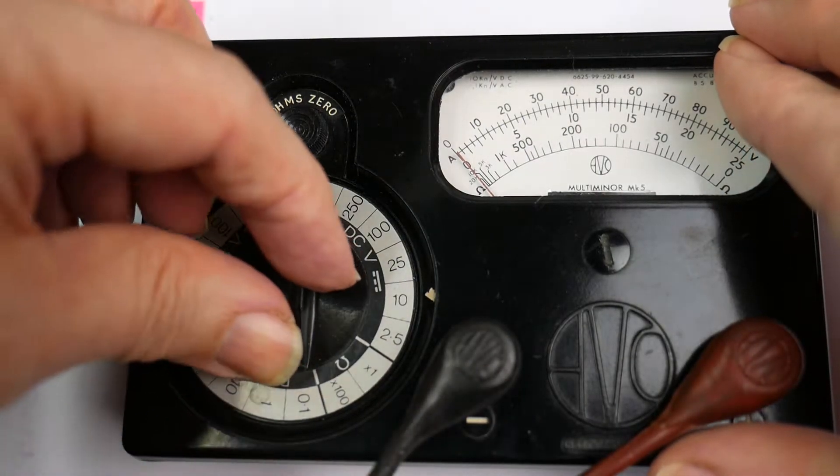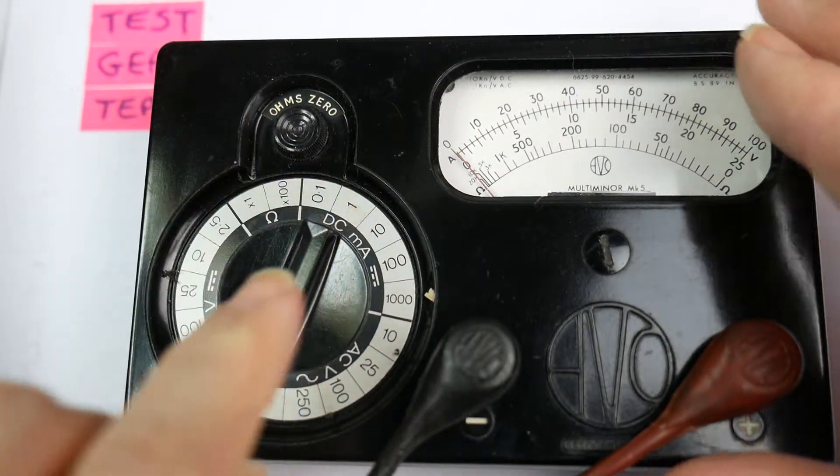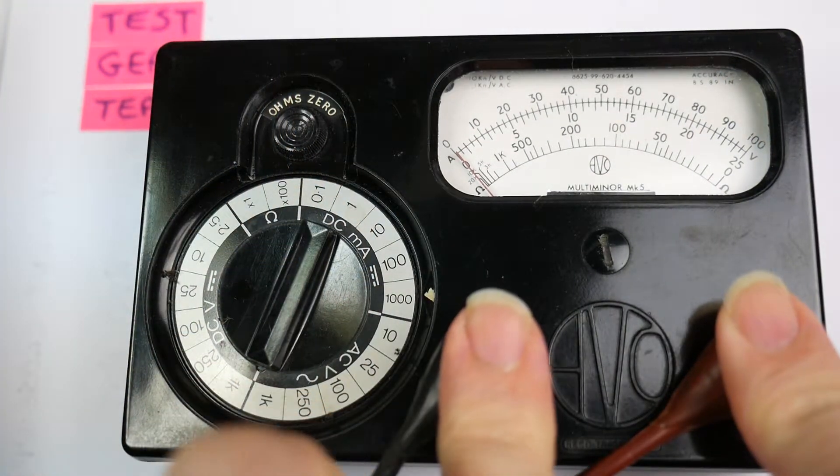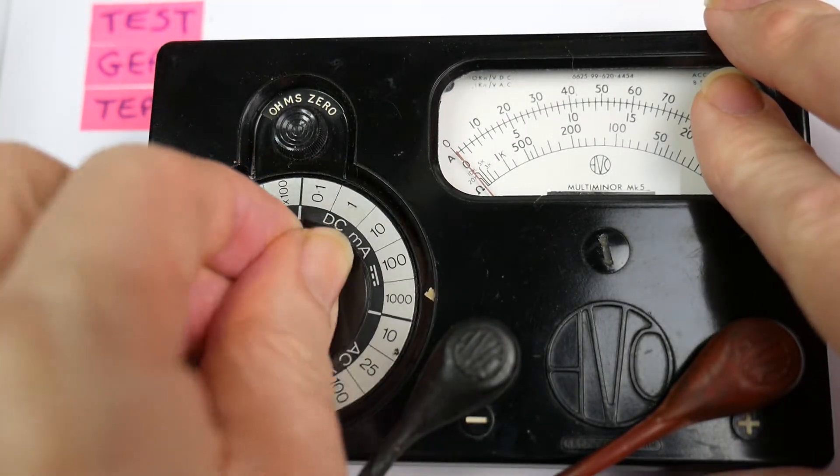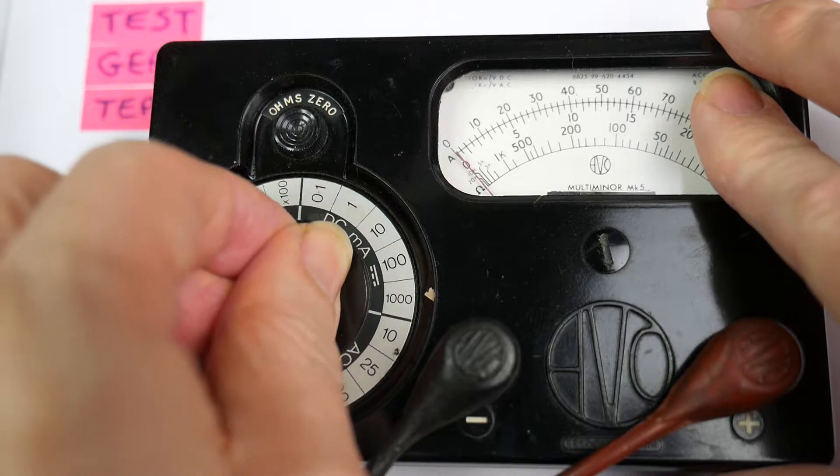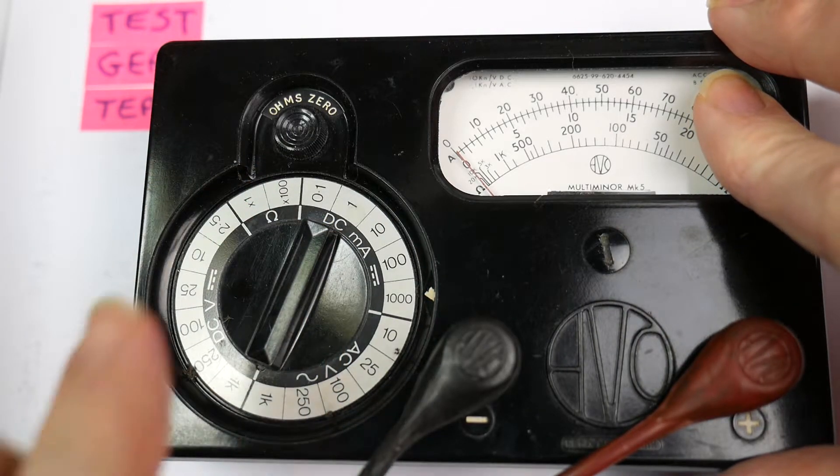If you switch to a current range, you don't have to change the leads over. So there is a risk if you were just turning this dial and you got round to the current ranges and you still had these attached to a voltage source—you're actually shorting the voltage source straight through the meter on a current range.